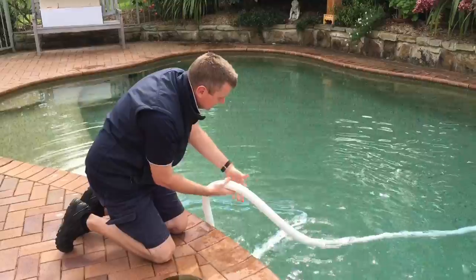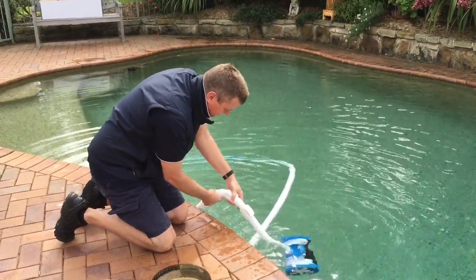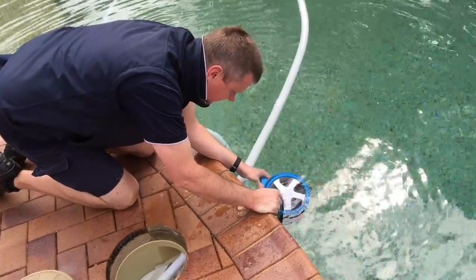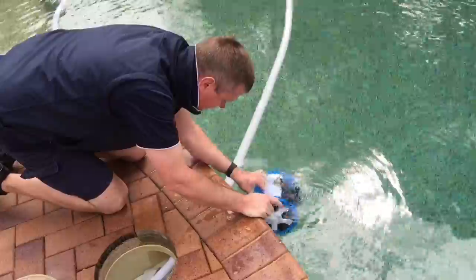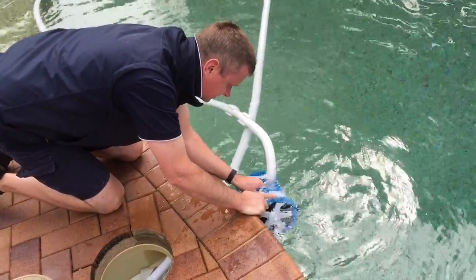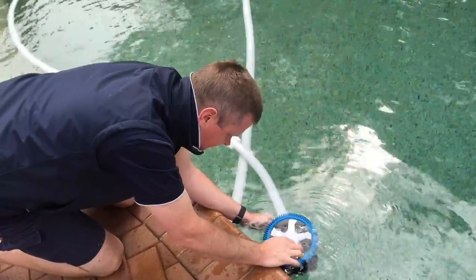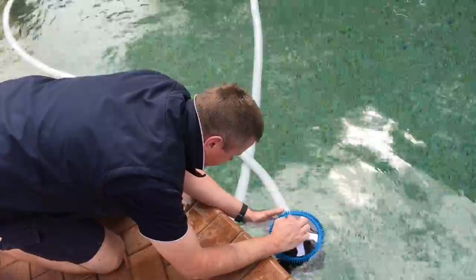We're going to check the speed now with the pump on medium speed. I'll pull it up so I can see what's happening with the wheel. These new ones have mag wheels so you can see clearly. You want the right-hand side wheel that constantly goes forward. I count — one Mississippi, two Mississippi — and aim for one full rotation in five seconds.